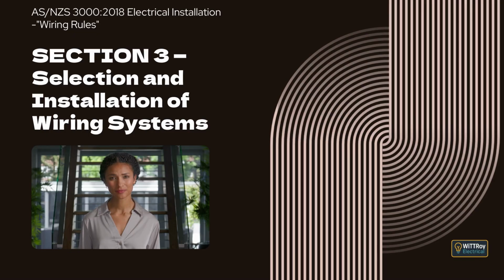Clause 3.9.6, Change of direction. This clause requires that changes in direction must not damage cables or place stress on insulation or terminations. Manufacturer bending radius limits must be followed, or minimum acceptable radii applied where manufacturer information is not available. Supports in contact with cables under pressure must not have sharp edges.